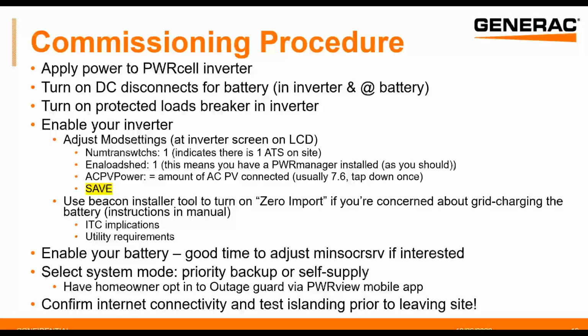Definitely test islanding, making sure the PV array turns on after a few minutes. When I say that, I mean the power cell inverter is triggering the third-party PV array to turn on, and that starts powering the house while simultaneously charging the battery. Then you can turn power back on to the house and show your homeowner that the system is operating the way you'd expect.